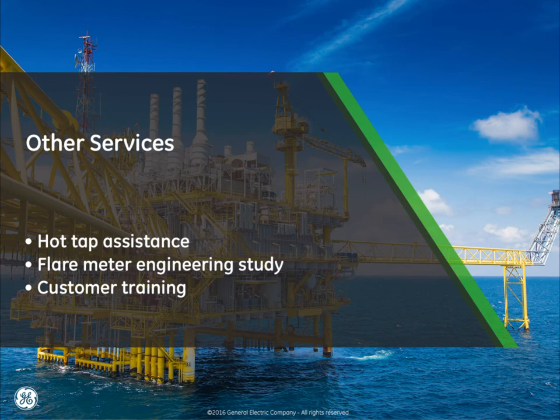The first is hot tap assistance. Ultrasonic flare meters can be purchased as a flow cell, or they may be hot tapped to a live flare line. In cases where a hot tap is warranted, it's critically important that the nozzles are properly aligned on the pipe. Ultrasonic flow meters only allow for one degree of tolerance between two transducers, which requires all steps of the hot tap to be completed with precision and accuracy. Your OEM should have trained representatives to assist the hot tap and weld teams to satisfy these difficult alignment requirements.